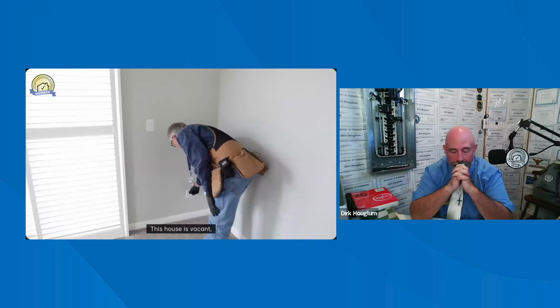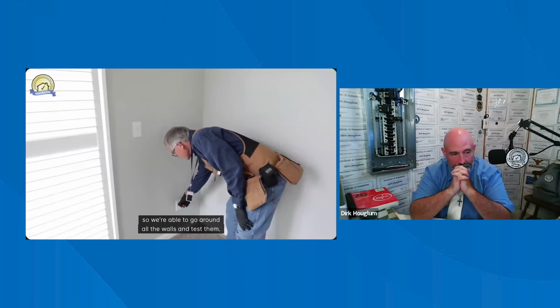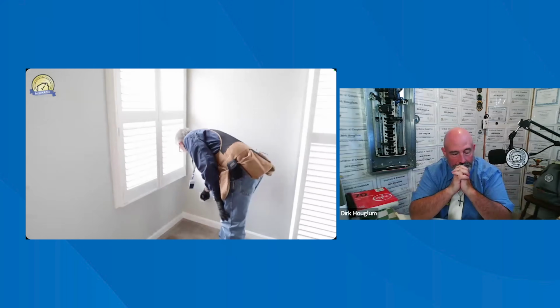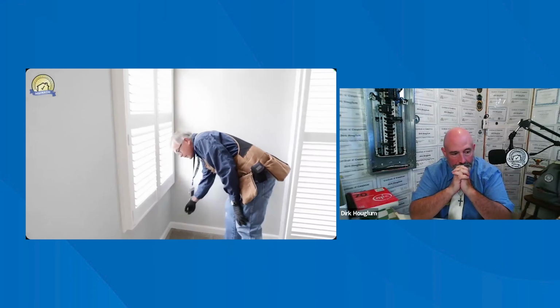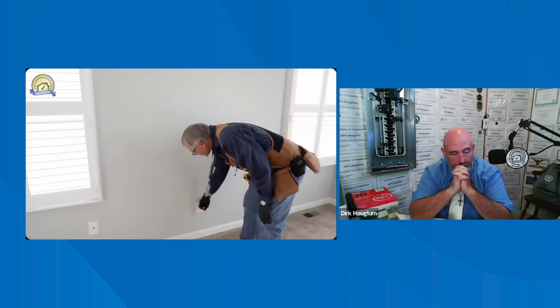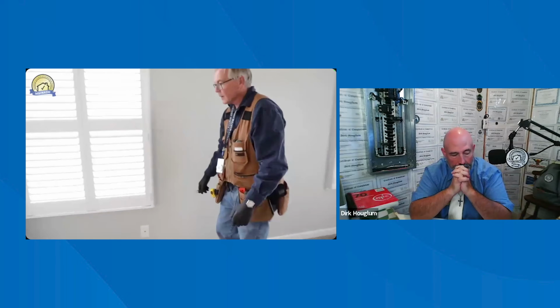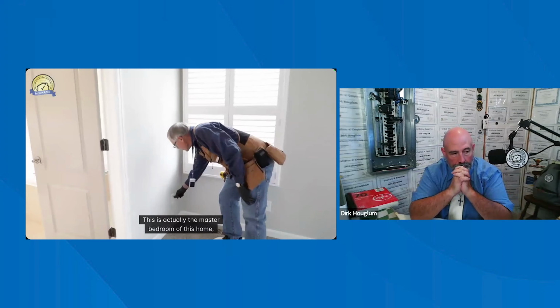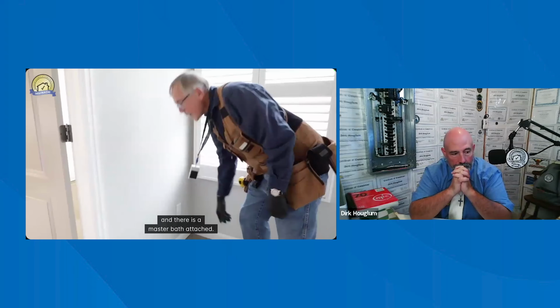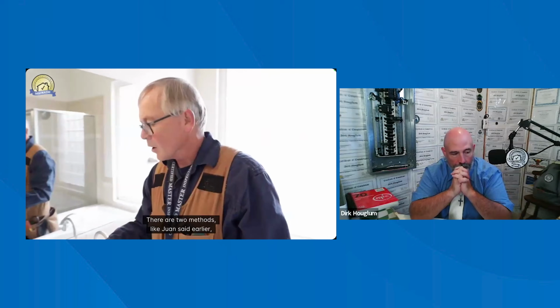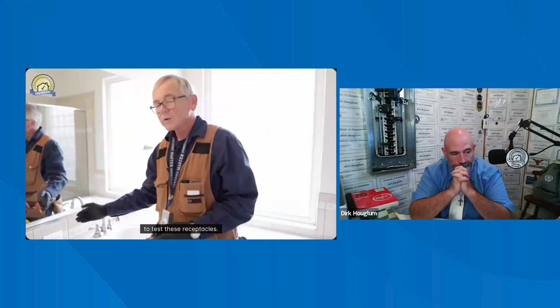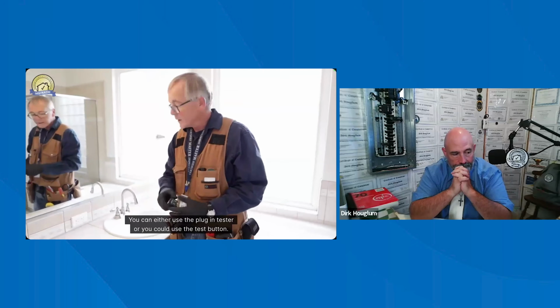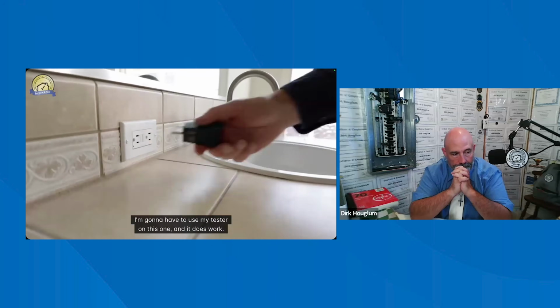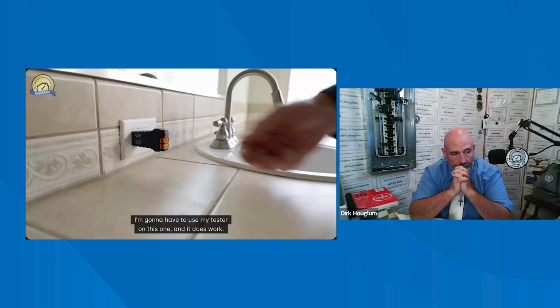This house is vacant, so we're able to go around all the walls and test them. This is actually the master bedroom of this home, and there is a master bath attached. So I'm going to step in there and test the GFCIs. There are two methods, like Lon said earlier, to test these receptacles. You can either use the plug-in tester or you can use the test button. I'm going to have to use my tester on this one, and it does work.